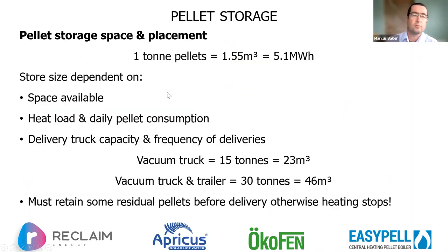And so our store size is going to be dependent, of course, on space, also on the heat loads and the daily pellet consumption, because there's no point having a massive store if they're not going to go through that much, which is what we see in schools quite a lot. But on the flip side, if we've got quite high consumption, we need to be thinking about a bigger store to make sure there's resilience and we're not having to have trucks going there every week, or ideally not going there every week. And so also the truck capacity and the frequency of delivery comes into it.